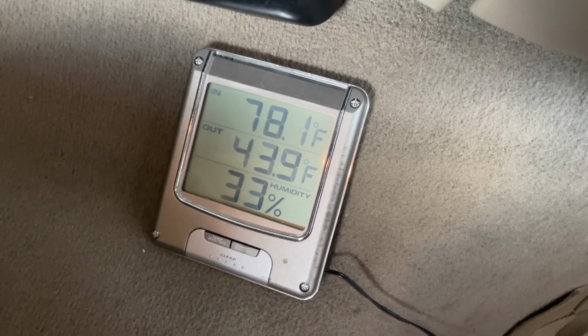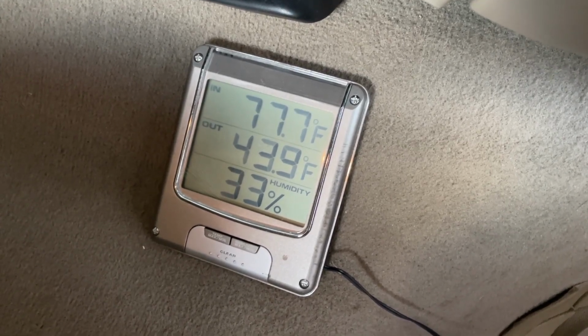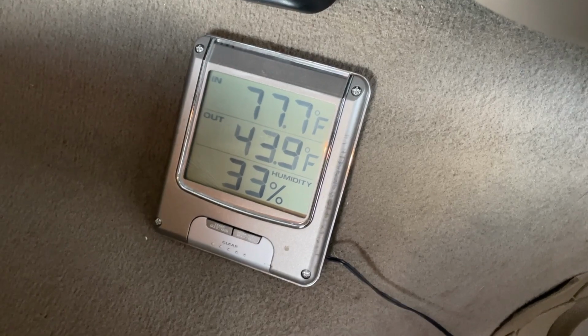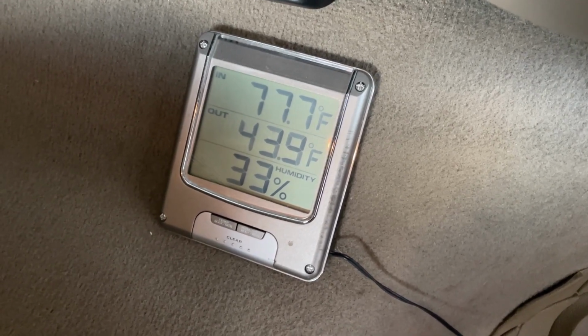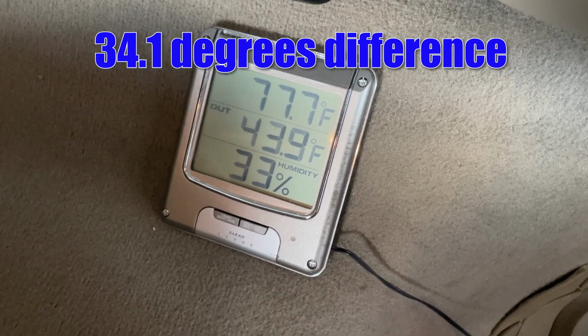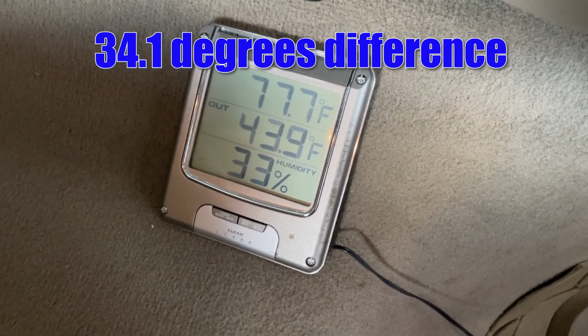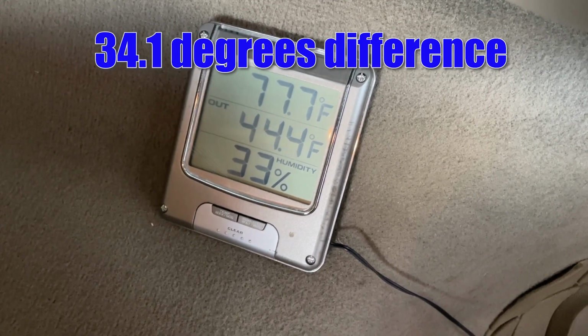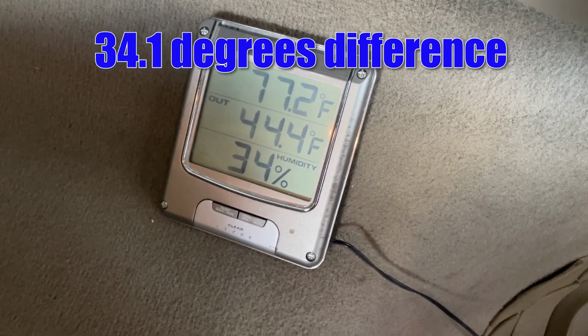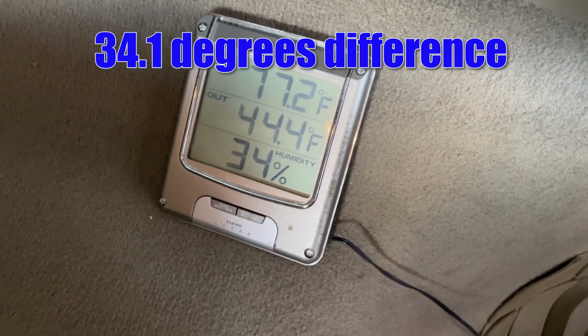To more accurately assess the ability of the system to absorb the heat load, we need to reference our ambient temperature reading to the air that's actually entering the evaporator housing. So let's see what happens when we reference our ambient temperature reading to the temperature of the air actually entering the evaporator housing with the recirculation door closed. As you can see, the difference is close to the same as we saw when the recirculation door was open and we were referencing outside air temperature. The key is that both temperature comparisons are providing an indication of just how well the system is removing the heat load. This is the 20 or 30 degree difference that I mentioned at the beginning.